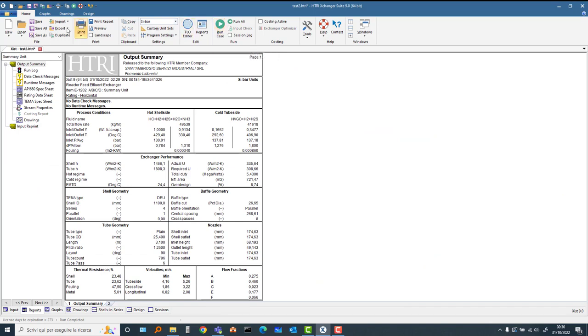Well, okay, we have a small increase of the pressure drop, but no substantial increase of the margin. I would say that the margin is a little bit decreased, even of some small percentage. Why? This is always because of the Tinker method, which considers the various streams and takes into account what is the really useful stream, the B-type stream, the stream which crosses all the baffles.